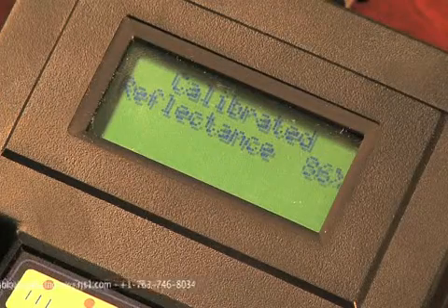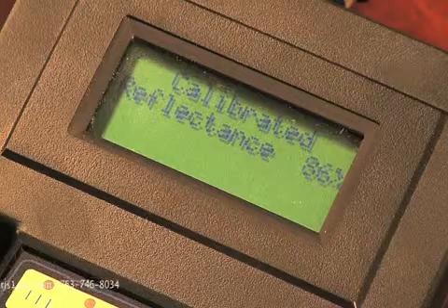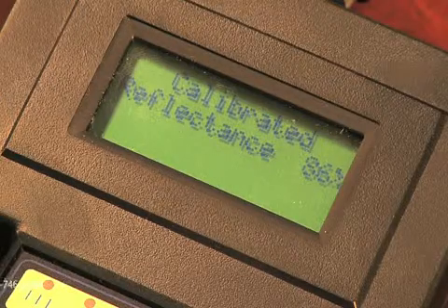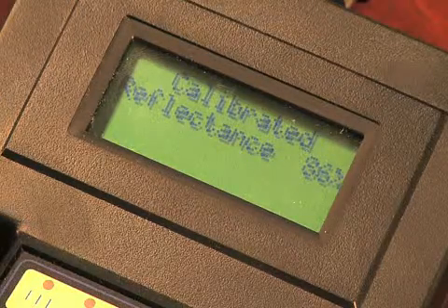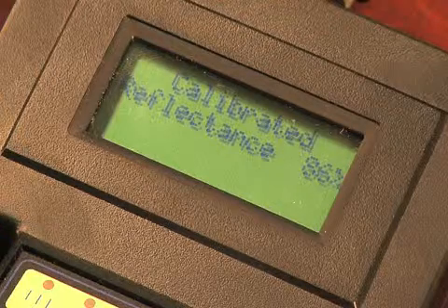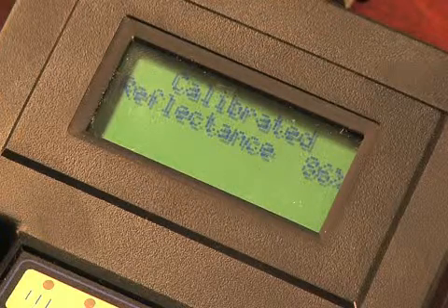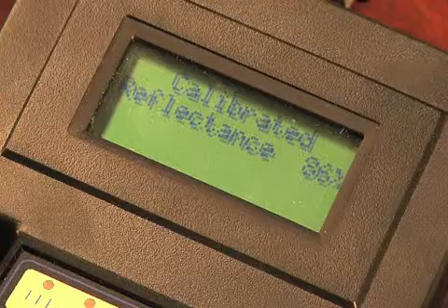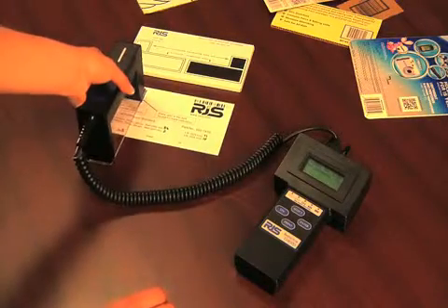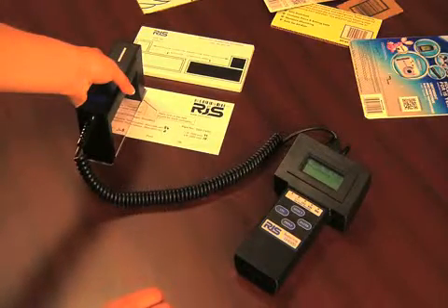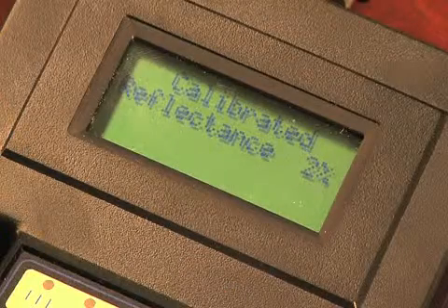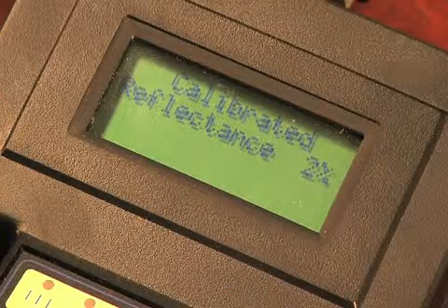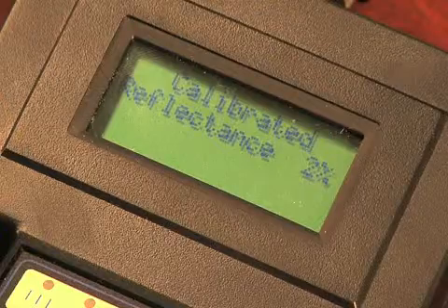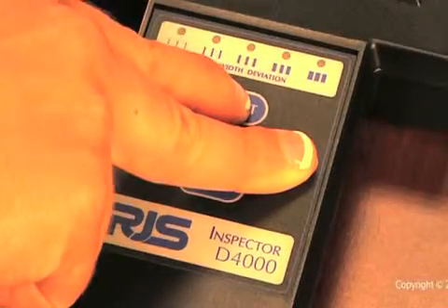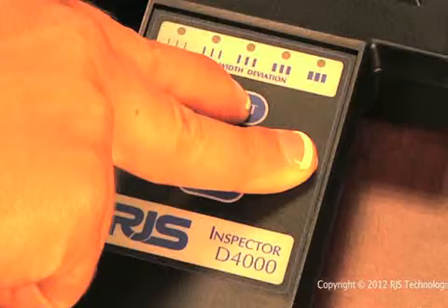My unit is reading 86%, and the plaque is also 86%. So the verifier is measuring the white value perfectly. However, plus or minus 2% is acceptable. Next, move the Auto Optic to the black square, and again compare the verifier to the plaque, and ensure it's within the same plus or minus 2%. If it is within 2%, press the Enter and Select buttons at the same time to exit the calibration screen.